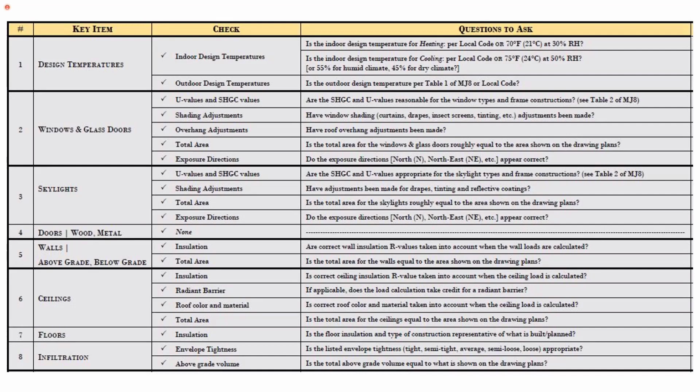You can get free tools that may not give you an actual Manual J, AKA approved document, in the end, but Wrightsoft, which is kind of the industry standard for doing HVAC design and load calculation, $300 gets you an annual subscription to use that. There's other tools that are $100 to $300, so it's not a major investment, especially if you're an HVAC contractor, to get the tool to give you these design documents at the end.